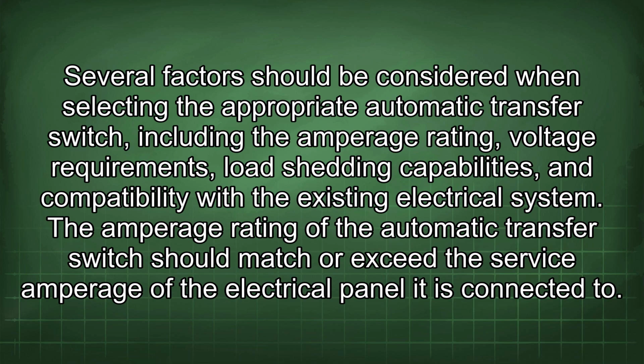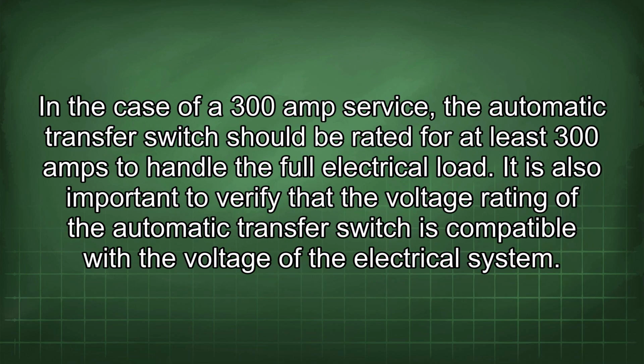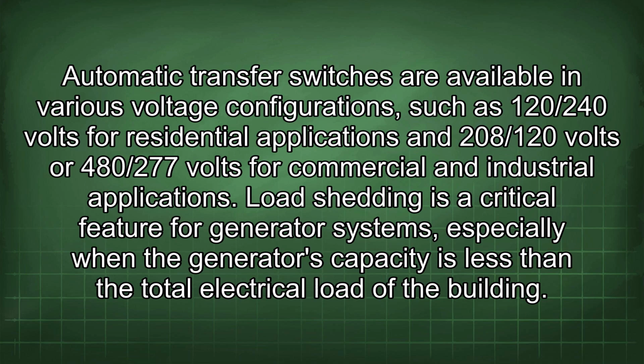The amperage rating of the automatic transfer switch should match or exceed the service amperage of the electrical panel it is connected to. In the case of a 300 amp service, the automatic transfer switch should be rated for at least 300 amps to handle the full electrical load. It is also important to verify that the voltage rating of the automatic transfer switch is compatible with the voltage of the electrical system. Automatic transfer switches are available in various voltage configurations, such as 120/240 volts for residential applications and 208/120 volts or 480/277 volts for commercial and industrial applications.